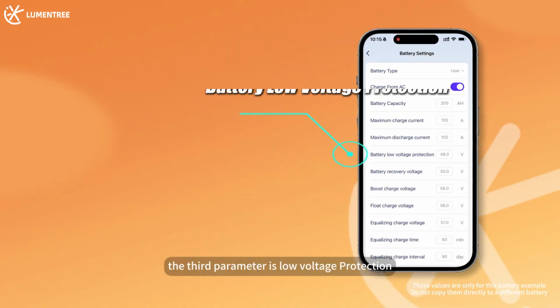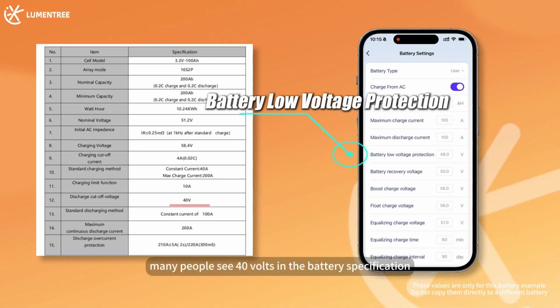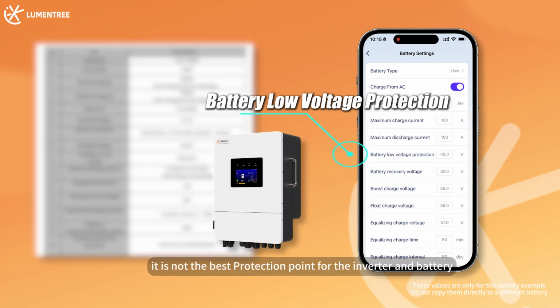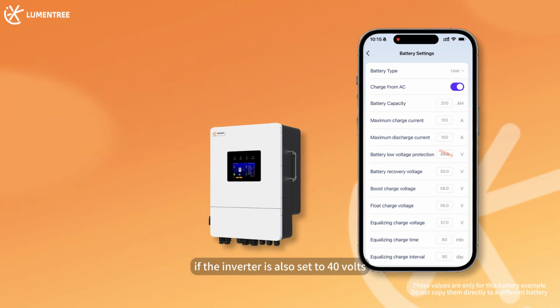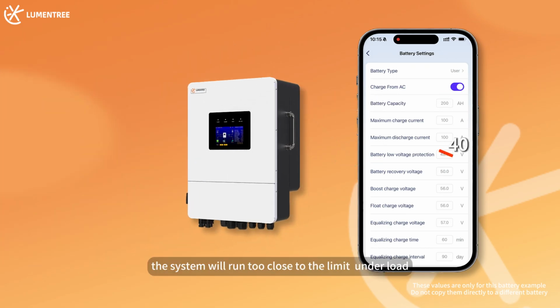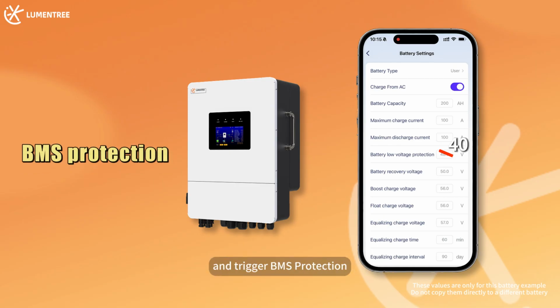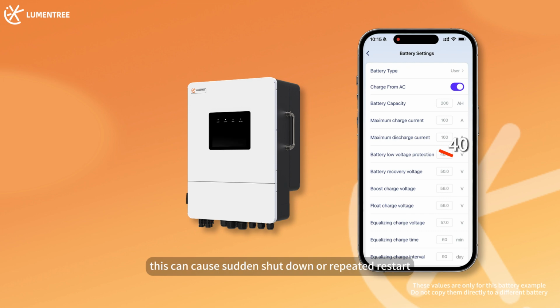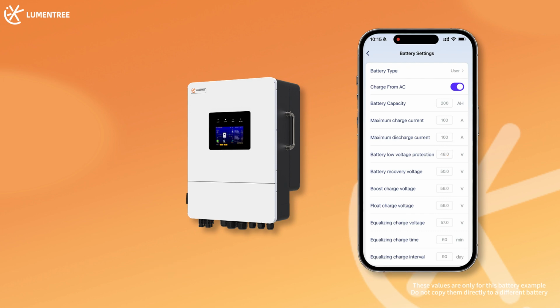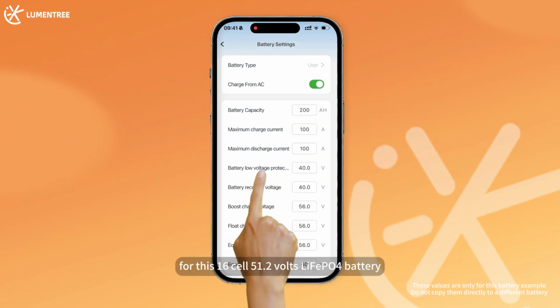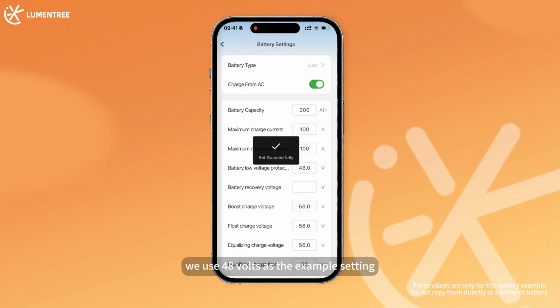The third parameter is low voltage protection. Many people see 40 volts in the battery specification and enter 40 volts directly into the app. This is not correct. The 40 volts in the specification is usually the battery or BMS cutoff limit. It is not the best protection point for the inverter and battery. If the inverter is also set to 40 volts, the system will run too close to the limit. Under load, the voltage may drop quickly and trigger BMS protection. This can cause sudden shutdown or repeated restart. So the inverter low voltage protection should be set higher than 40 volts. For this 16-cell 51.2 volts LiFePO4 battery, we use 48 volts as the example setting.